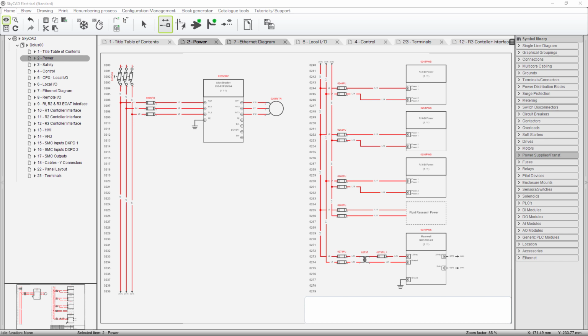Then we've got a power supply, 24 volt DC. I don't remember the amperage. I was thinking it was 8 amps or 10, 12 amps. I don't remember. So the only conductors leaving this page, going to another page, are the ones that have references. And that would be these two right here that are the 24 volts DC. That's 24 volts DC and that's 0 volts. They're going to another sheet, sheet 4 actually. You can't read the references, but it's going to sheet 4, and that's where we pick up the 24 volts DC. There's no AC leaving this sheet. If there were, then these 3 conductors right here, or 2 of them at least, would drop on down and have arrows down here like we do over here. So this reference right here references this arrow up here and so forth. So we transfer our 3-phase over to here, and then it stops here. No AC leaving this sheet.